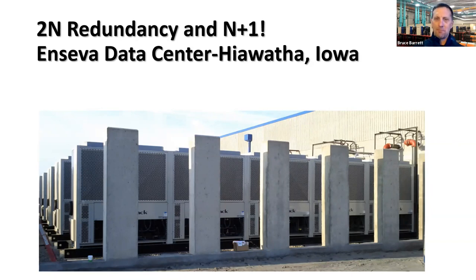So they had tremendous capacity redundancy. Even though they lost a flow switch, it wasn't an emergency to go in there and fix it. Once they discovered the flow switch was bad, the wire was chewed, less than a $150 replacement for that part. A little bit of labor, and they're off and running back at a full 2N capacity. I had to take this picture when the louvers were off. They called them hurricane louvers in Iowa, but high wind, tornado louvers really in the end.